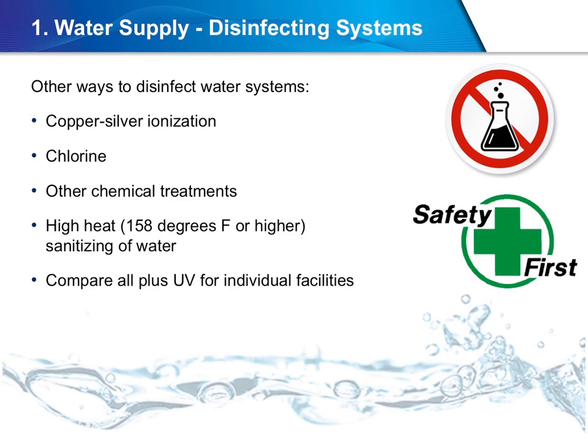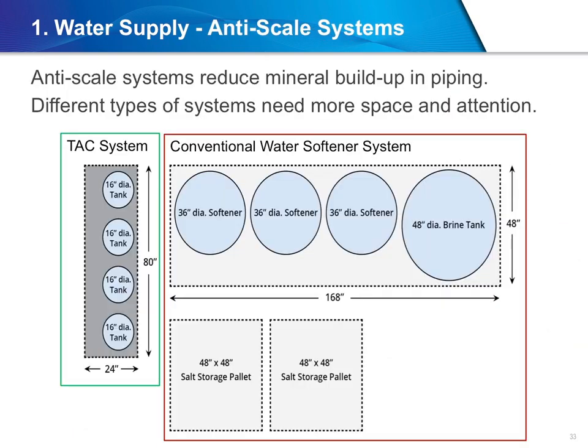Chlorine and other chemicals have been utilized for Legionella and other bacteria control. The main disadvantage to chlorine is that it can be very corrosive to piping and other equipment. In cases of hyperchlorination, corrosion can cause pinholes to develop in piping. And as mentioned before, heat can also assist in the control of Legionella.